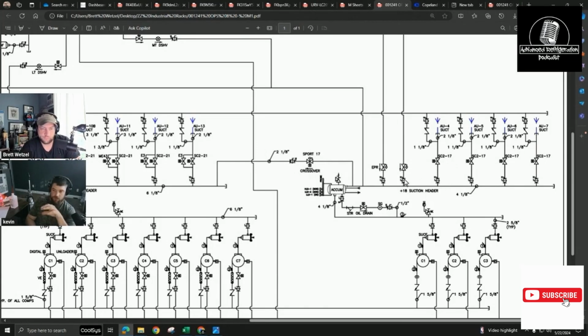You should only be shutting off down to like one compressor. You don't want it so loaded that it takes all the load off the other side, because that's killing your efficiency. You want it just loaded enough that if you were to lose load on the low side, it's going to pick up some. It depends on how it's programmed, right?